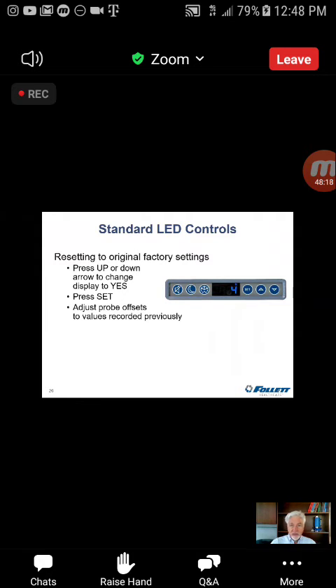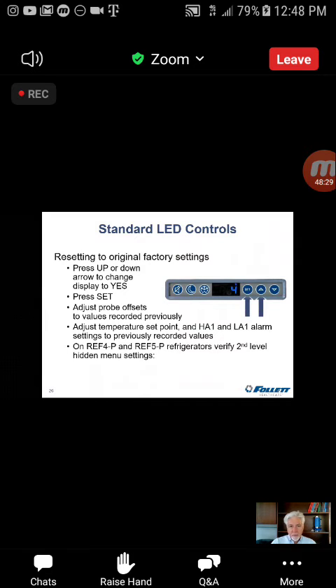And then all we need to do is go back into our offsets, our temperature setting. We just change those all back to what they were that we recorded, if they were anything other than the factory settings. One other thing, on REF4Ps and REF5Ps, we made some changes to that. We made some changes to several of those settings, and they weren't from the original ones. We found that we could enhance the unit's performance by making these changes. So the original units may have had these enhancements manually set in, and when you do the hard reset, you take them out because you're going back to the original settings.